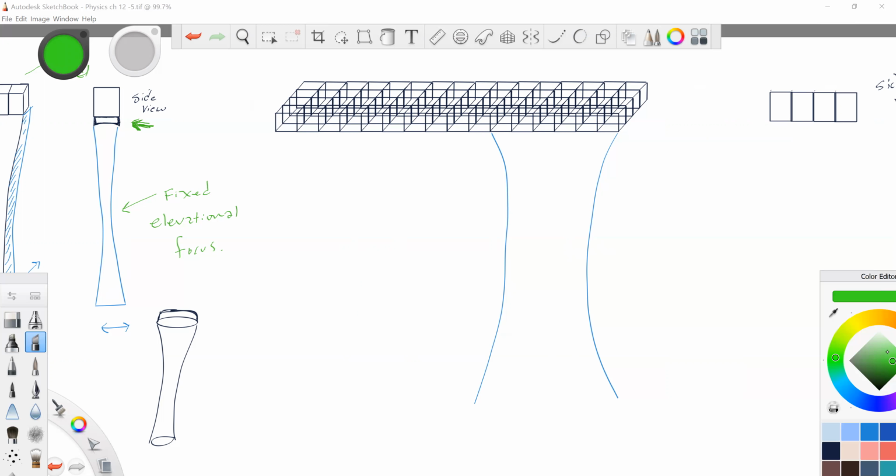But newer transducers called 1 1/2 dimensional arrays create thinner beams with improved slice thickness. Unlike traditional linear, phased and convex probes, which have a single crystal occupying space, the 1.5D array has multiple crystals in the up and down direction. Back and forth, up and down, across and back.